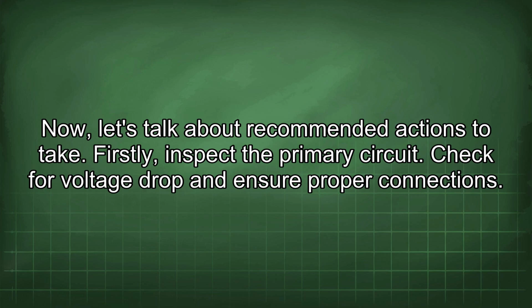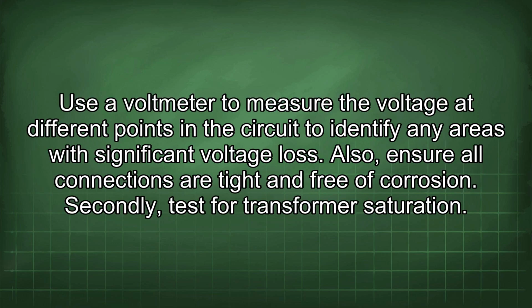Firstly, inspect the primary circuit. Check for voltage drop and ensure proper connections. Use a voltmeter to measure the voltage at different points in the circuit to identify any areas with significant voltage loss. Also, ensure all connections are tight and free of corrosion.